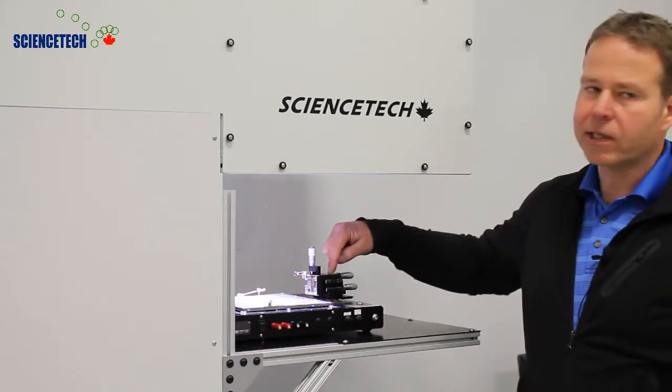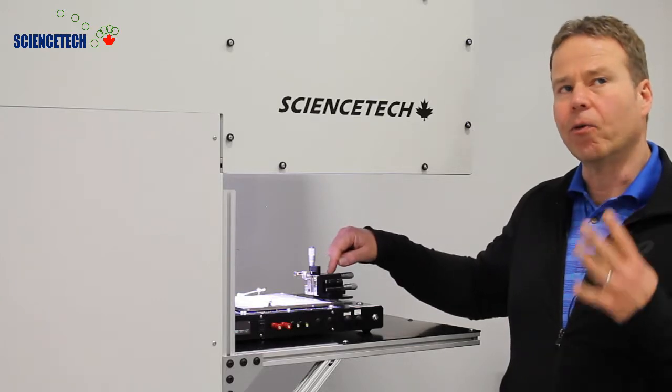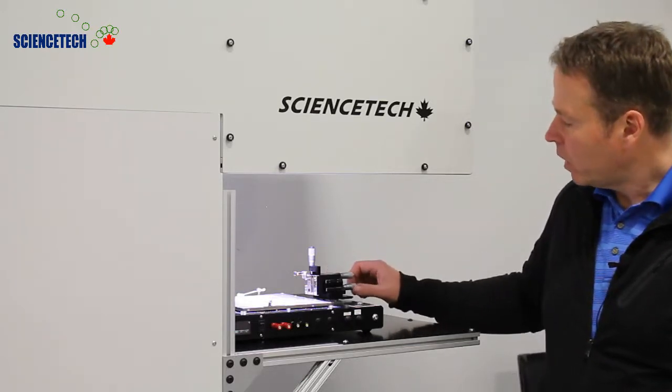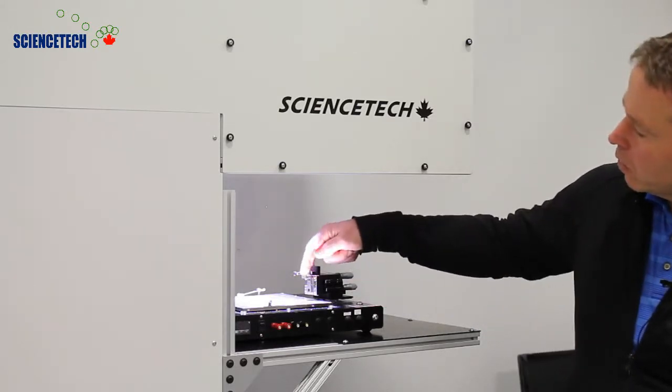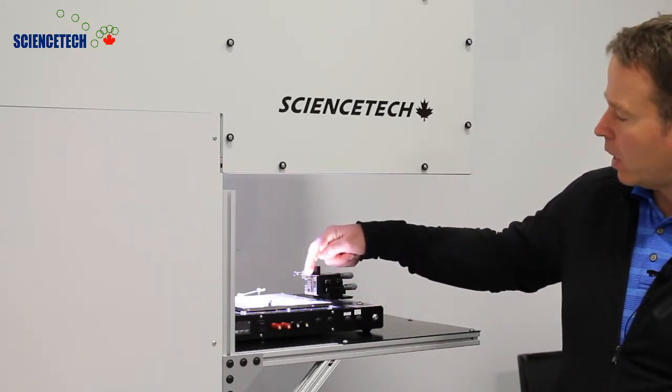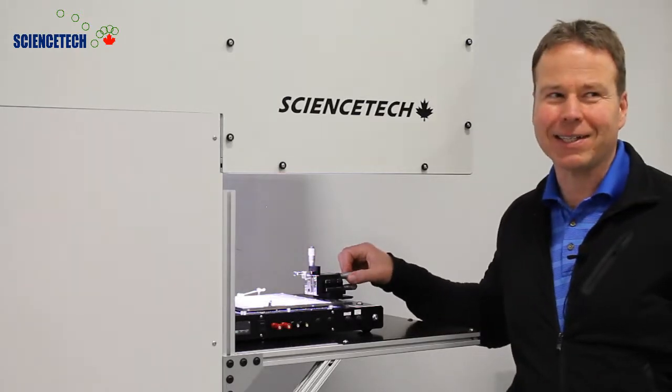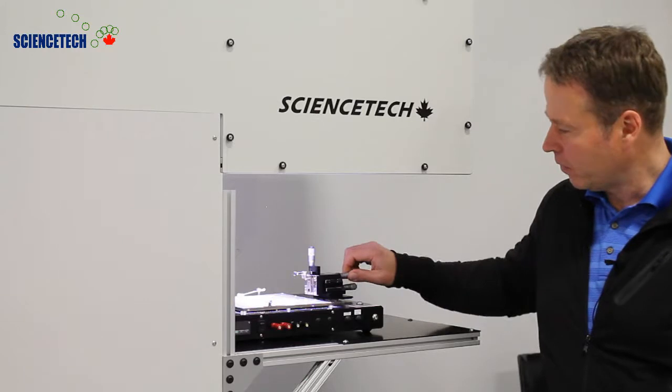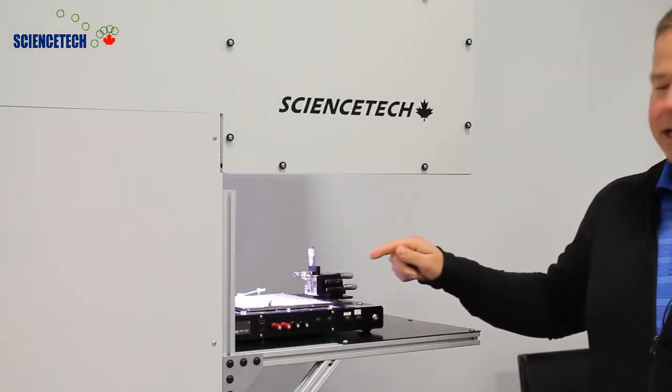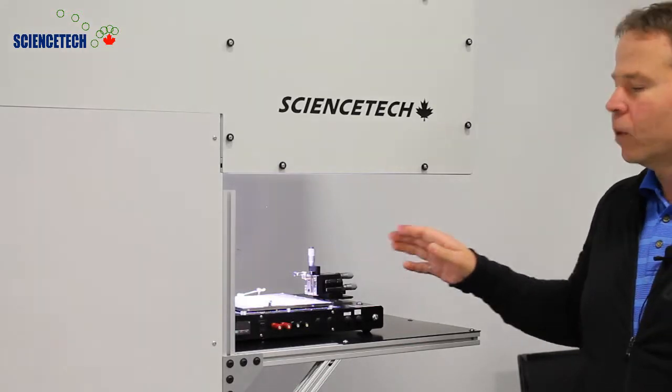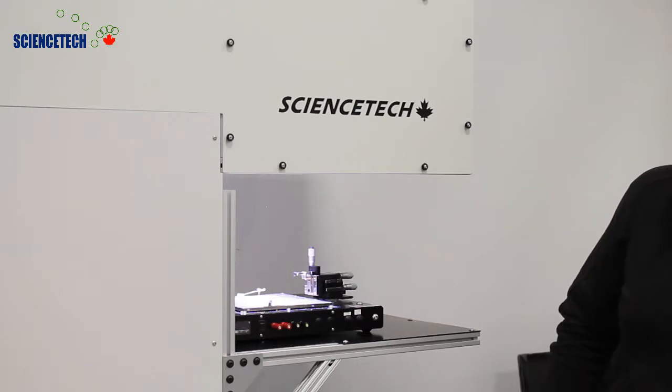Here, this configuration allows for one contact, but we also allow for four contact measurements, and it's micrometer controlled. Normally we would have a tungsten or gold-tipped pin here, but for safety's sake it's not in here so I don't poke myself. And we can move the pin around in three dimensions to precisely place it on the contact, which would allow us to do IV measurements of the solar cell.